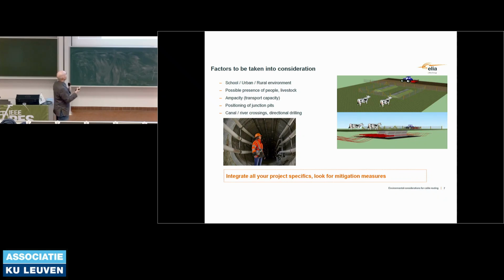The ampacity or transport capacity is also a factor - you need cables especially for that, but having them close together can be harmful. The positioning of junction pits also matters, if you want to apply cross-bonding. Junction pits, especially for land cables that come on drums, are needed every 750 to 1,000 meters, and somebody has to crawl in and make these delicate junctions.